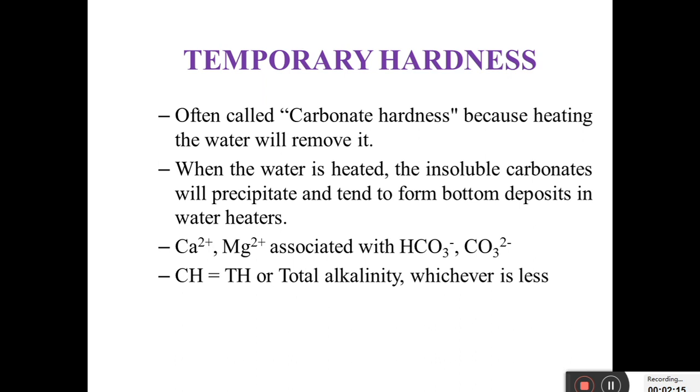First of all, temporary hardness. As I told you, it is often called carbonate hardness because by heating the water, that temporary hardness will be removed. When the water is heated, the insoluble carbonates precipitate and tend to form bottom deposits in water heaters. It involves calcium and magnesium associated with bicarbonate and carbonate. Carbonate hardness or temporary hardness is equal to total hardness or total alkalinity, whichever is lower.